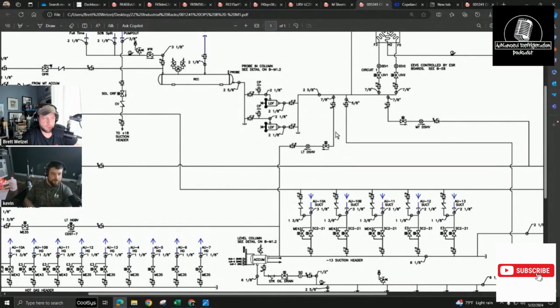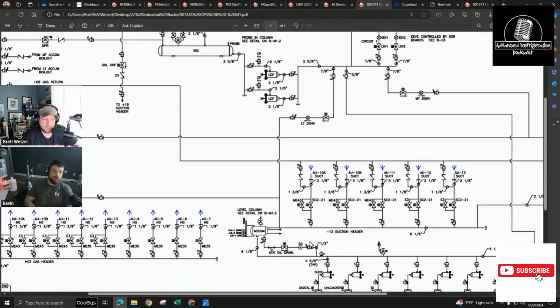No, but I'm saying it's de-superheating. So it's dumping liquid in here to drop the temperature down. If it goes into defrost too long, or it's bringing it back. So that's something I've seen Zero Zone do lately. They've been adding liquid injection and hot gas injection on all their racks.